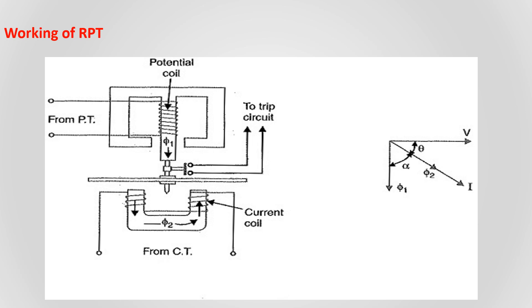The working of the reverse power relay: it has two coils — one for PT (potential transformer) and another for CT (current transformer). Sometimes the relay will have a cross-coil construction. We use two coils because we need to calculate power. The basic formula for power is voltage multiplied by current, which is why we use both a PT and CT. Another question is: why calculate power and not current? Because it is difficult to determine the reverse current direction in AC.